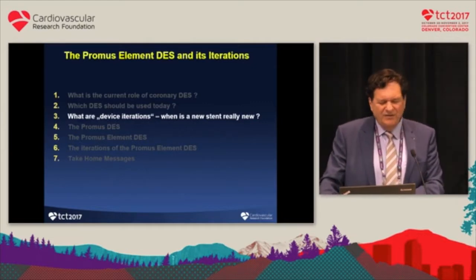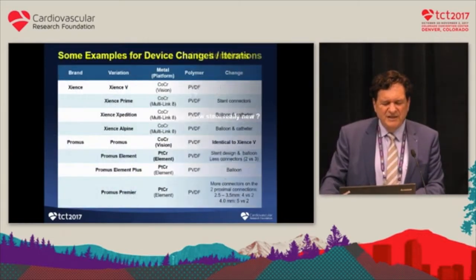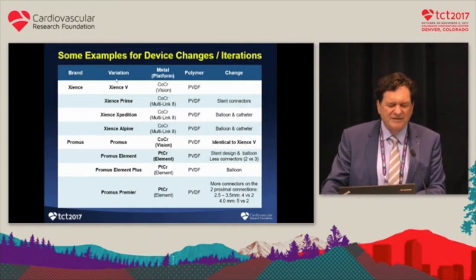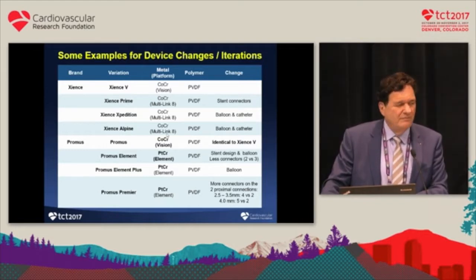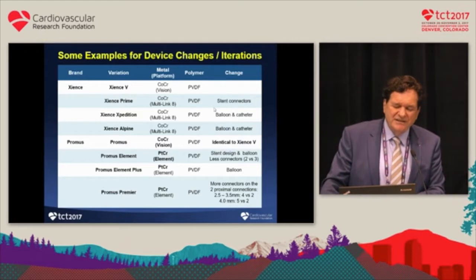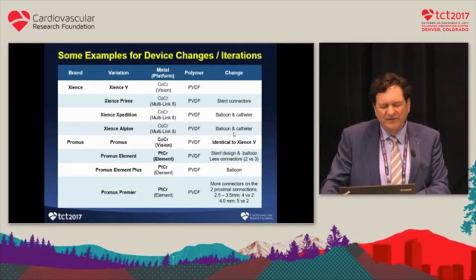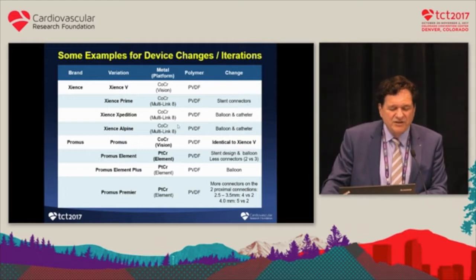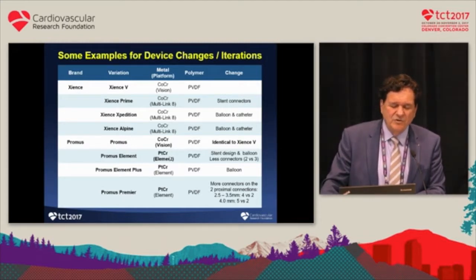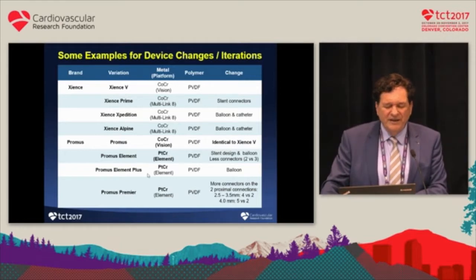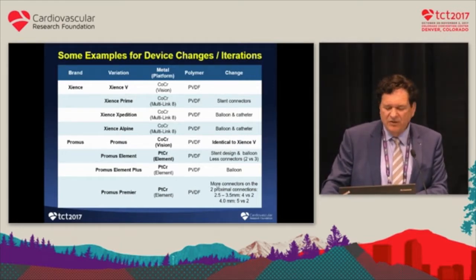What are device iterations, and when is a new stent really new? As examples of device iterations, modifications of the Xience stent started with the Xion V, then the Prime, the Expedition, and now the Alpine — but they all have the same metallic platform, the same polymer, and just little changes in the balloon and catheter. These are not really major modifications. But a major step forward was from Promus to Promus Element — Promus and Xience were the same stent, but the Promus Element went from cobalt chromium to platinum chromium.